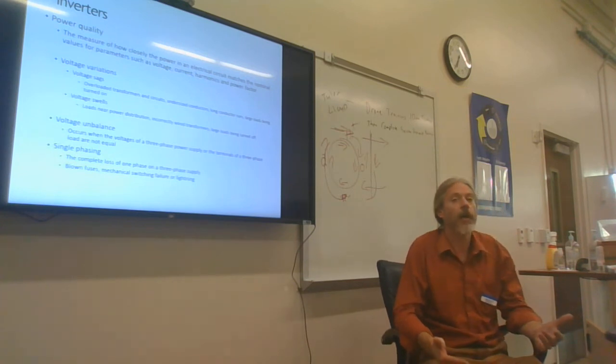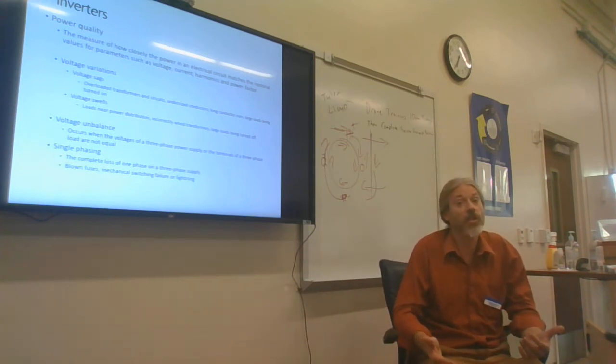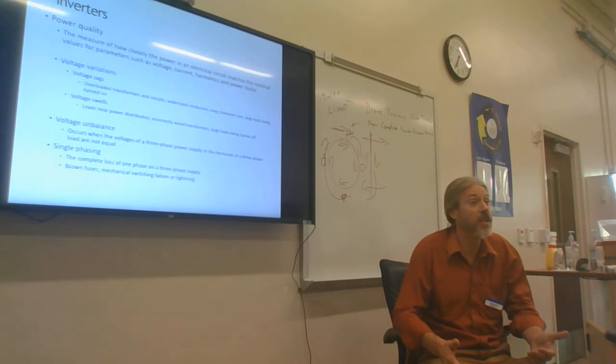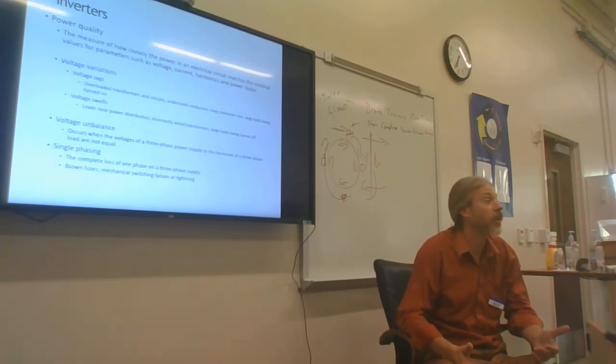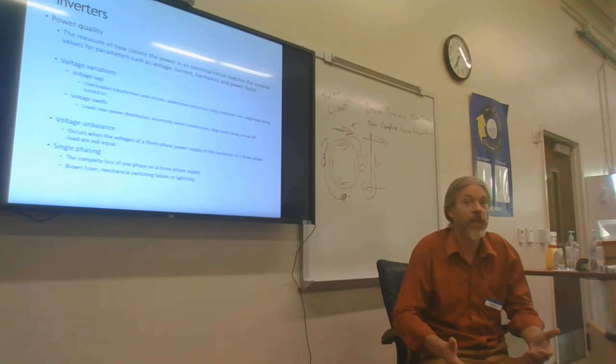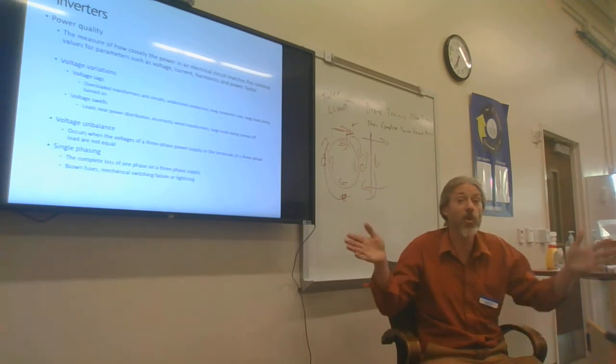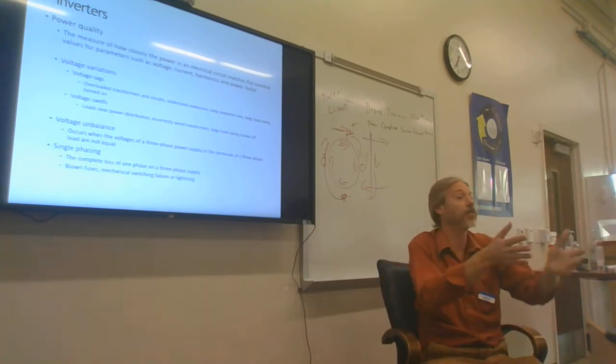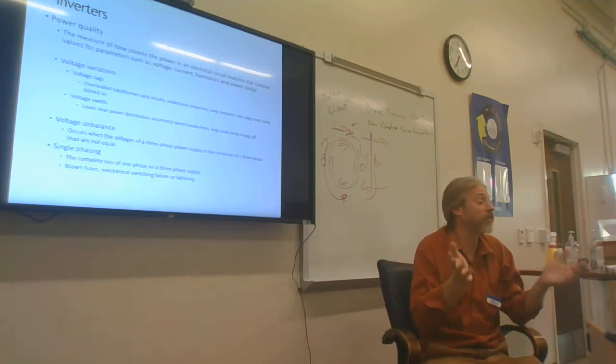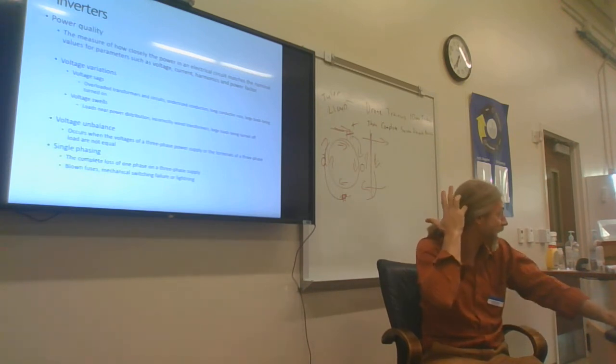All right. It's also a really big reason that you can never, ever, never run DC conductors in the same conduit as AC conductors, because those DC conductors would 120 times per second be negatively affected by the AC voltage changes. So when we have storms and we have electric lines that are being blown in the wind, that can actually cause both voltage swells and sags.